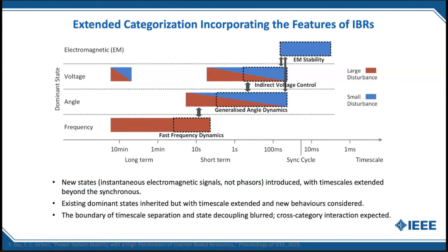When we turn to inverter-based resources within a system, we see a couple of things change. First, we see much faster effects — electromagnetic modes developing in the millisecond region that won't be picked up in phasor models. We also see frequency dynamics becoming elongated, with some effects at very short timescales, seconds or sub-second. That means they start to overlap with the angle dynamics, and we get coupling between those. The angle dynamics become faster as well and start to couple into the voltage dynamics, substantially complicating the traditional separation that enables analytical insights.